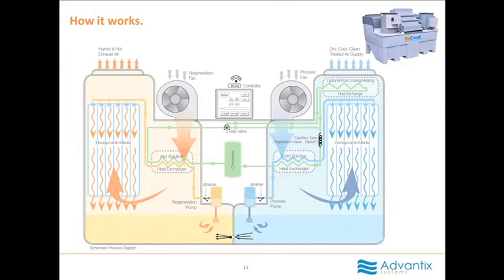But what's happening now is it's the same as the 2 cups, but we're adding a lot of stuff in order to accelerate that process, and a couple of things in order to get a heat transfer effect that's going to be useful for us. So what are we adding to accelerate the process? Rather than just wait for air to interact with the surface of the water, we're going to bring the liquid up to the top of a media bed. This is like a honeycomb media. And we're going to bring air in under the force of a fan and bring that up from the bottom.